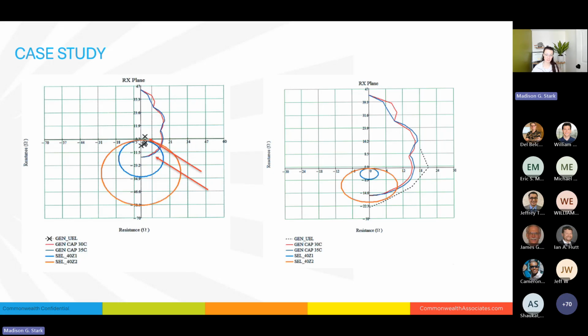What we want to see over here is much better. So as we come from the outside in, the first thing we hit is this limiter, perfect, going to curtail operations. Then we hit our zone 2 slow acting relay, perfect. Then we hit our generator capabilities, and then we hit our zone 1 relay, instantaneous trip. So that's a lot more of what we're looking for in the coordination element to protect the generator.